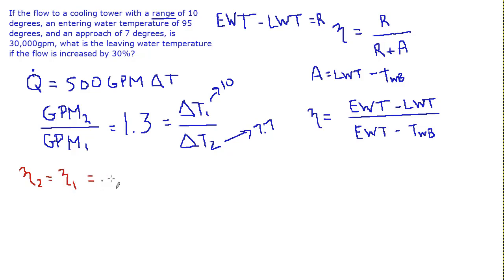We'll say efficiency 2 equals efficiency 1. And what does efficiency 1 equal? We know entering is 95. We know the range is 10. So we know the leaving is 85 in the original case. And we know the approach is 7. We knew the leaving was 85, so the wet bulb must have been 78. So that gives us the ability to plug it in at this level or plug it in at this level. The range is 10. And the range plus approach is 10 plus 7, which is 17. So the efficiency is 0.588.